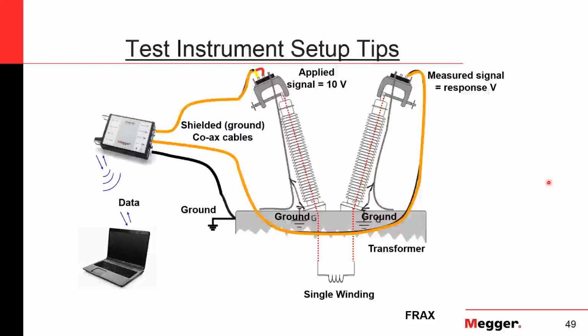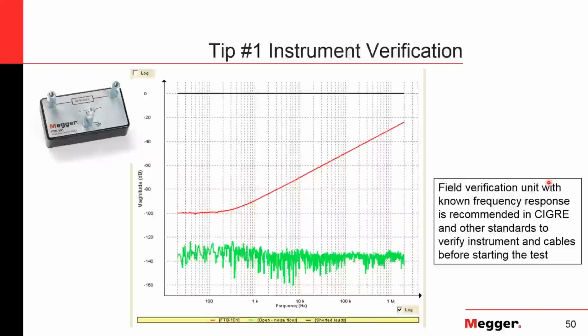One is have a reference here, like some kind of verification over the whole frequency range and a variety of decibel responses. So you have this known response, and if you go through and you get the same response, your equipment's doing well.